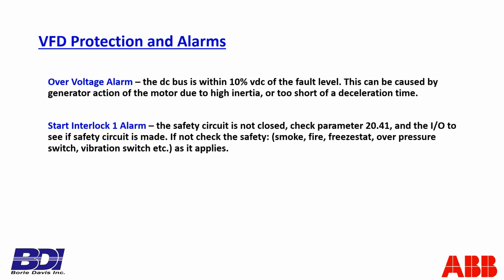The overvoltage alarm is implying that generally we may be seeing some generator action from the motor, similar to the overcurrent alarm. Overvoltage is not a shutdown. It's a statement that this load, we're probably trying to decelerate it, but the inertia is too high to decelerate it in the short time that you've got programmed in.